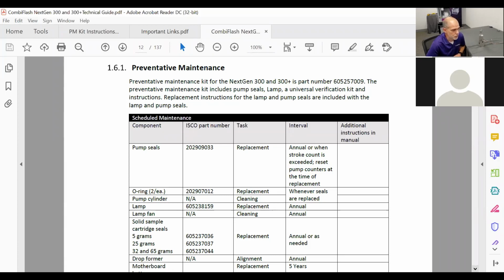The lamp needs replaced pretty often. I've seen lamps last as long as 7 years. I've seen lamps last as long as 7 months. Now, the average lifespan of a lamp is probably going to be somewhere around 2 years. And that's with daily on and off of the unit. We do recommend that you replace the lamp annually, though, as we do recommend a PM kit annually. But it's up to you what you want to do. But we really recommend a yearly replacement of seals and lamp.